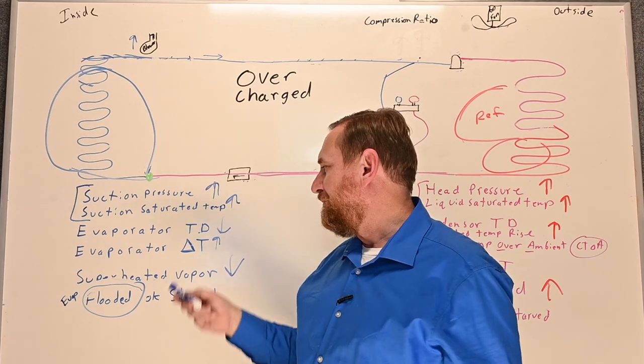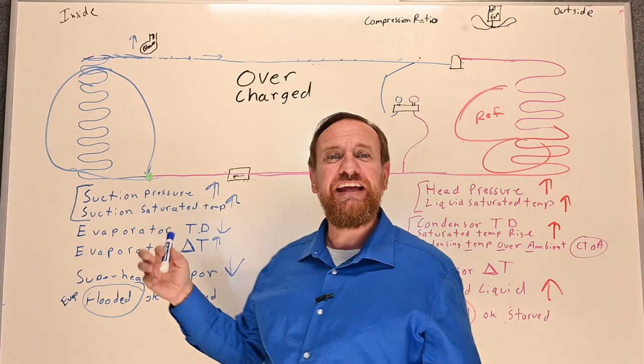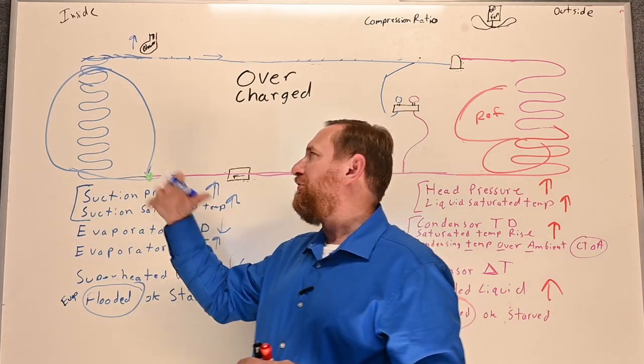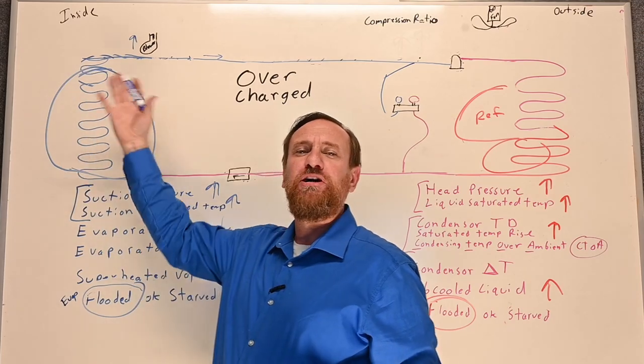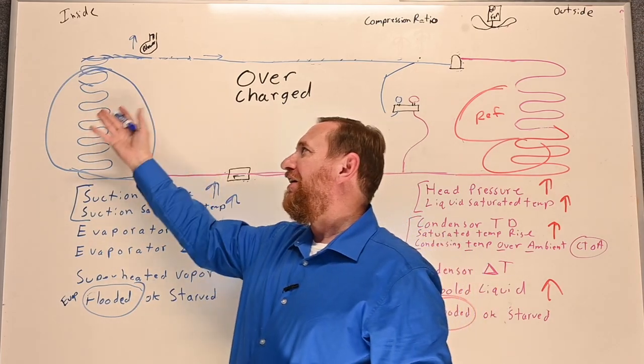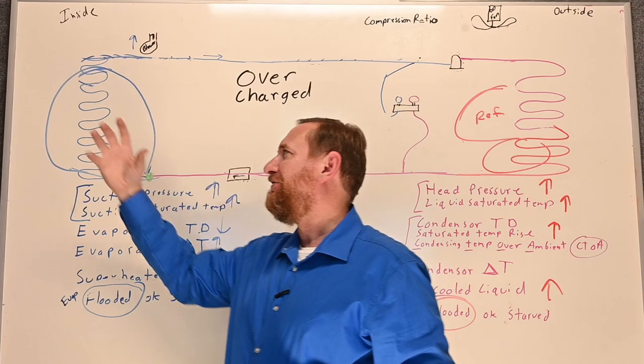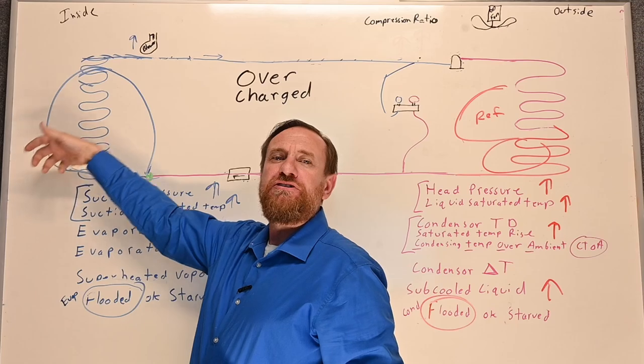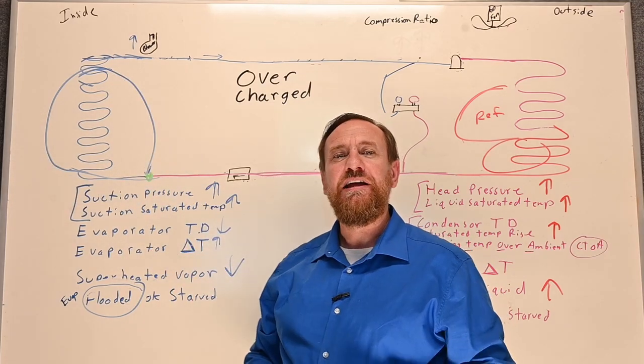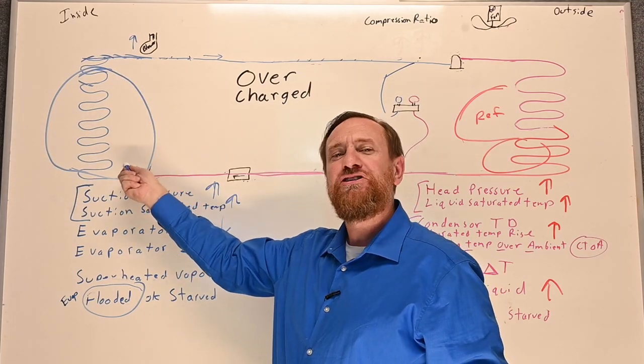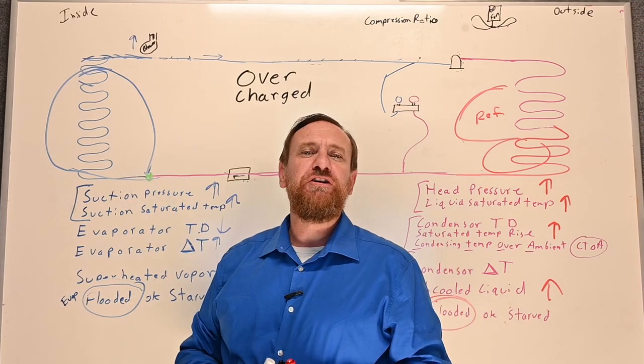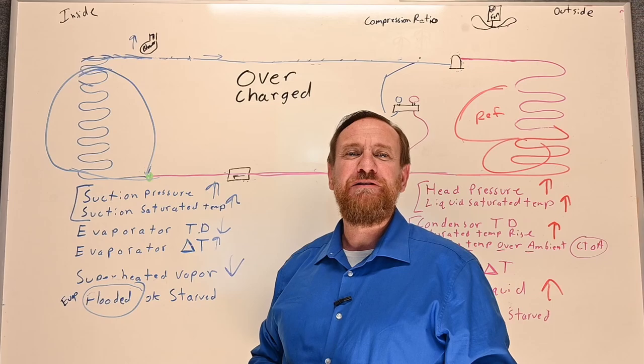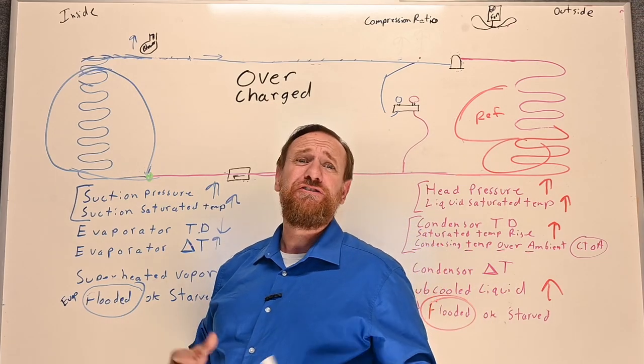A lot of people overcharge systems because they only look at the evaporator delta T number. They think if they force more refrigerant into that evaporator coil, they get more saturation and absorb more heat — and to an extent they are absorbing some more heat, dropping the air temperature more. But because your saturated temperature is higher, it's also farther away from the dew point, which means less dehumidification. And we know that's going to be an issue — dehumidification is essential for air conditioning.